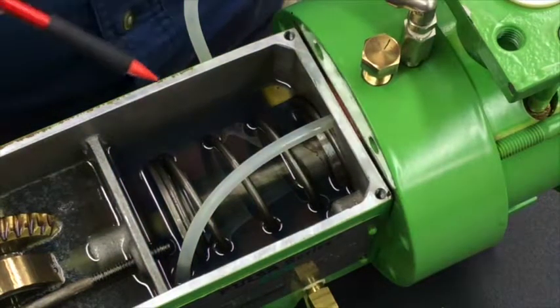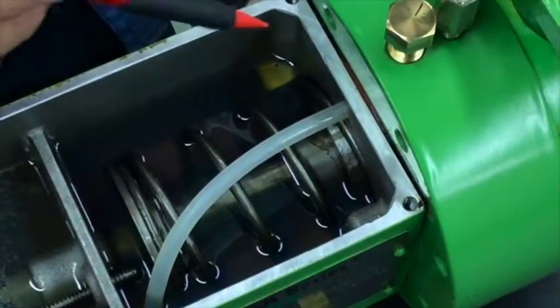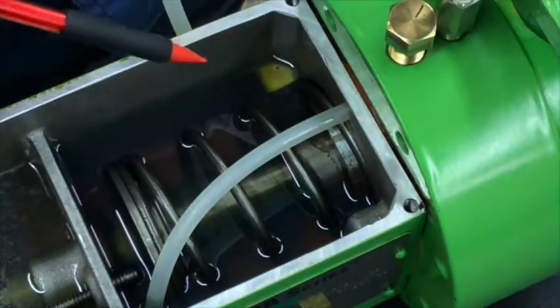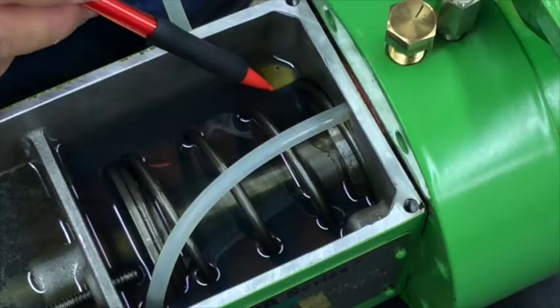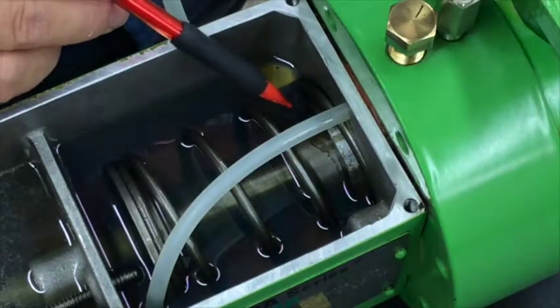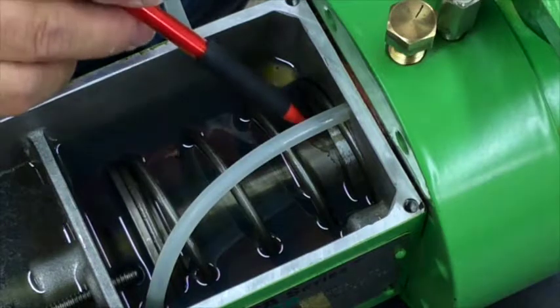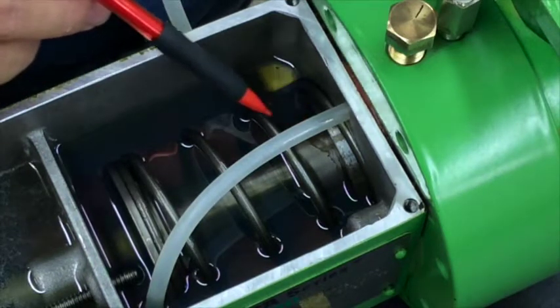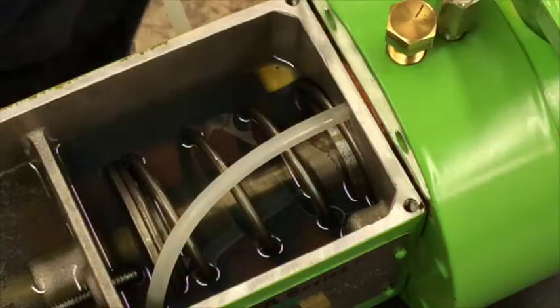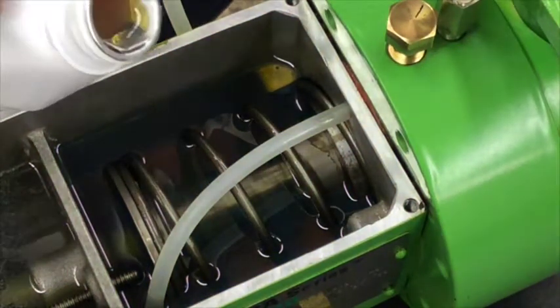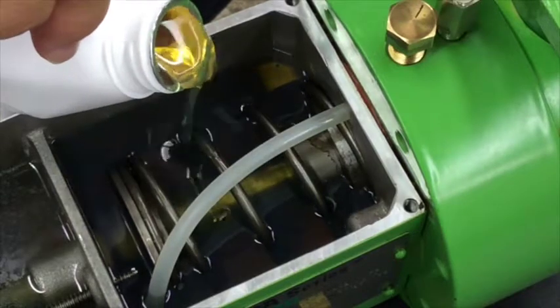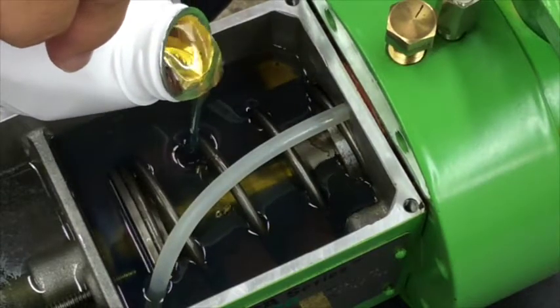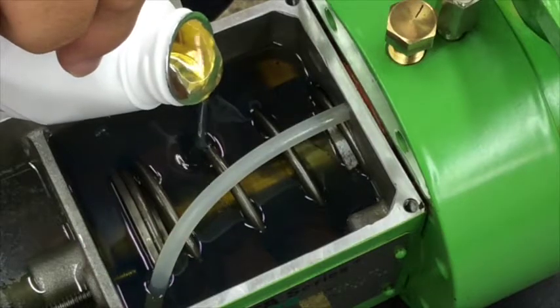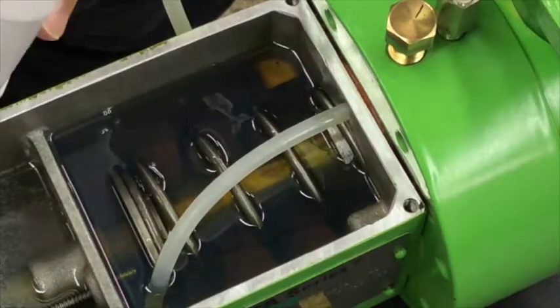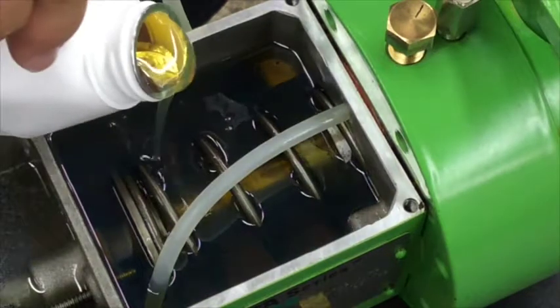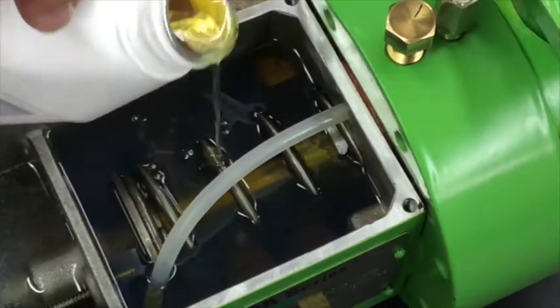Right, we've begun the process of filling the pump head with oil. And what's happened is that the oil level inside this chamber has dropped a little bit. What I want to do is raise that oil level so that I'm covering this piston as it enters and exits the cylinder. So I'm going to quick grab the oil here. And that's probably enough right there. Maybe a little more, huh? All right.